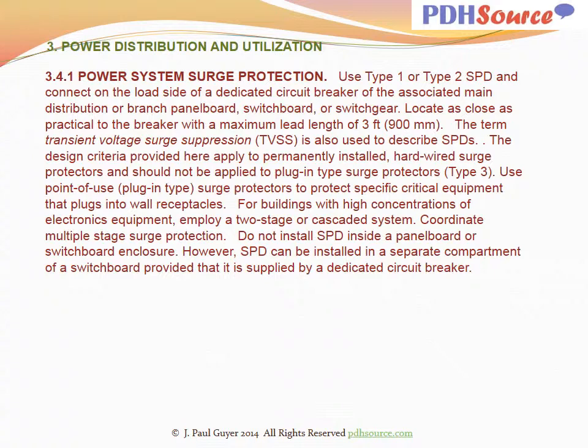The design criteria provided here apply to permanently installed hardwired surge protectors and should not be applied to plug-in type surge protectors, Type 3. Use point-of-use plug-in type surge protectors to protect specific critical equipment that plugs into wall receptacles. For buildings with high concentrations of electronic equipment, employ a two-stage or cascaded system. Coordinate multiple-stage surge protection. Do not install SPD inside a panel board or switchboard enclosure. However, SPD can be installed in a separate compartment of a switchboard, provided that it is supplied by a dedicated circuit breaker.